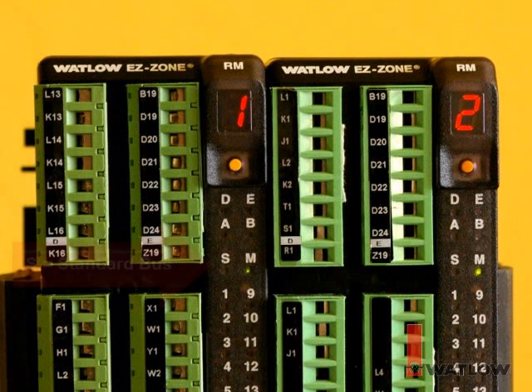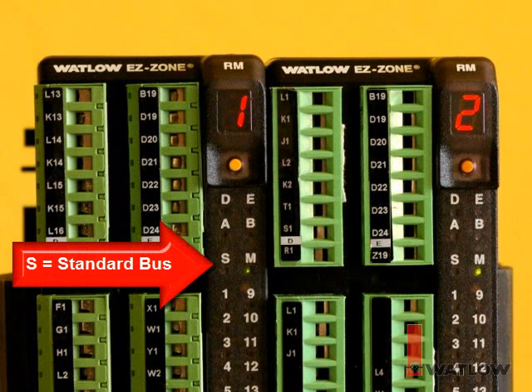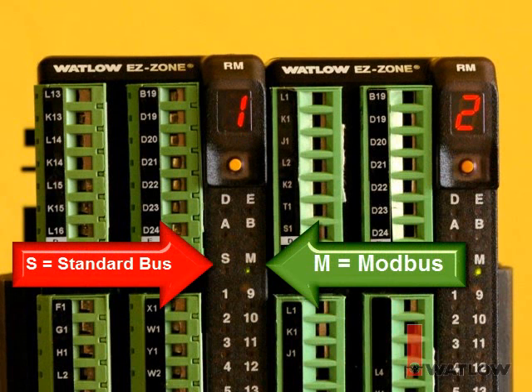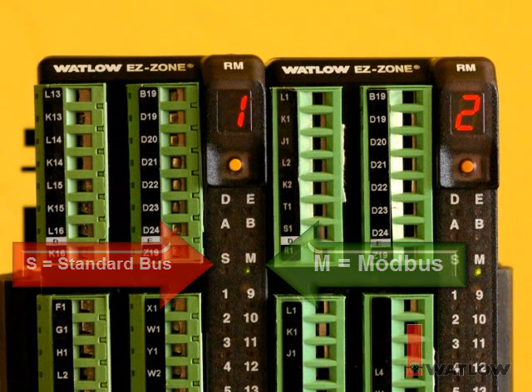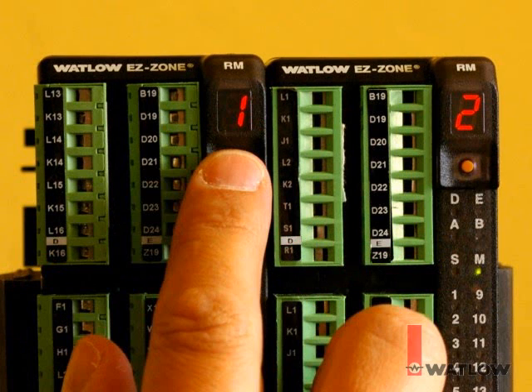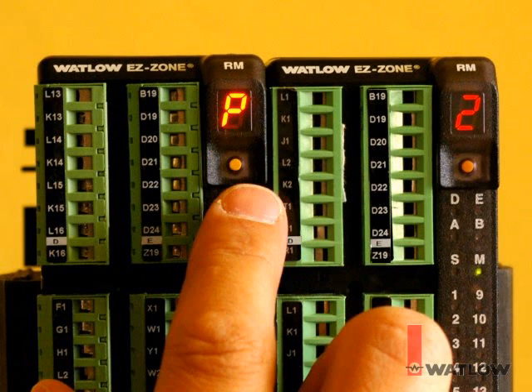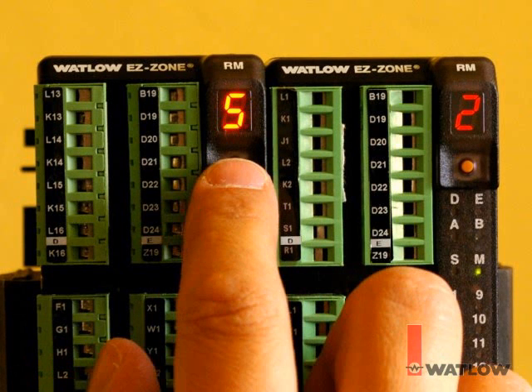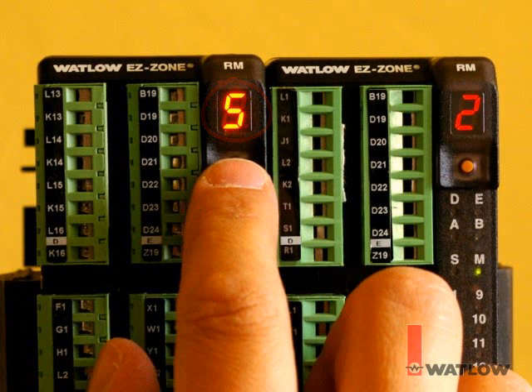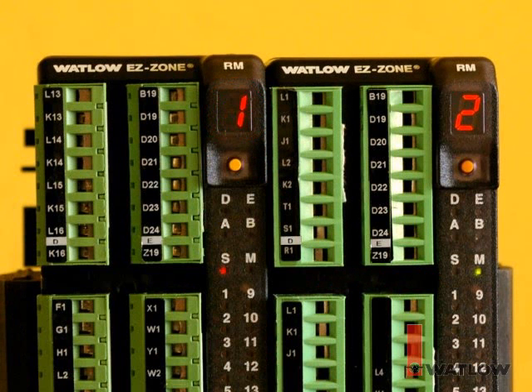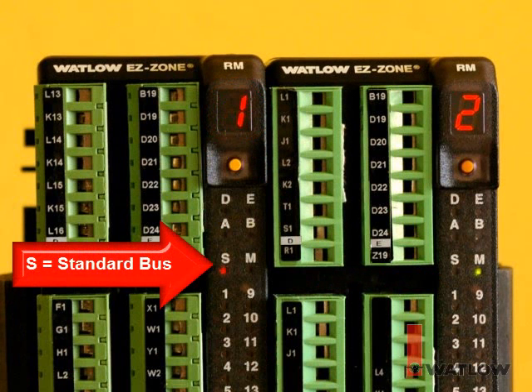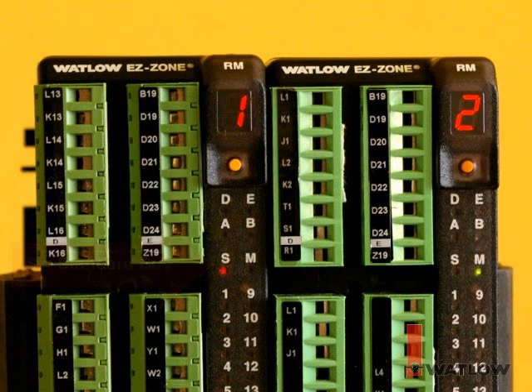The protocol setting is shown by the indicators, S for standard bus and M for Modbus. To change the protocol, press the button and hold it until the letter P is displayed. Then press the button once to switch the protocol to standard bus. The display shows S for standard bus as we make the change. Also, the M indicator goes off, and the S indicator comes on to show the module is set for the standard bus protocol.